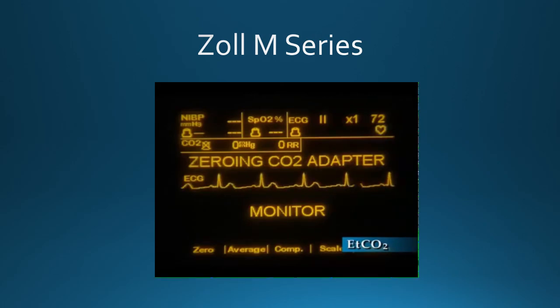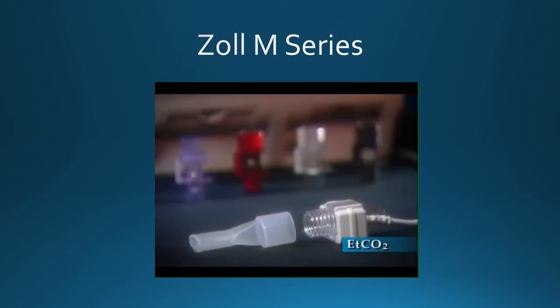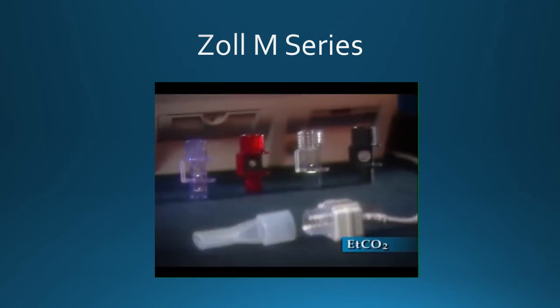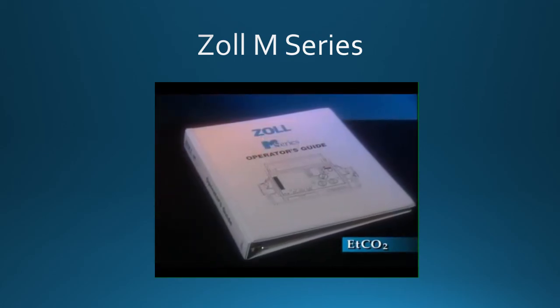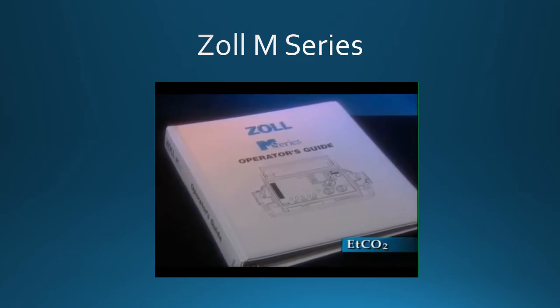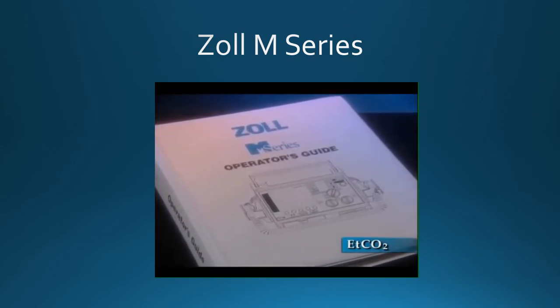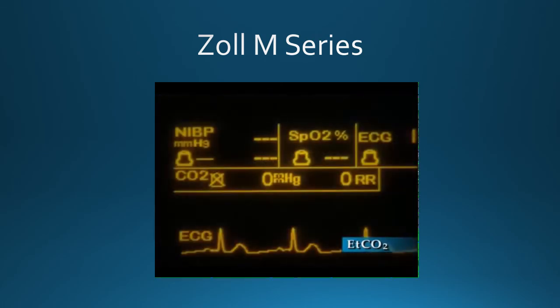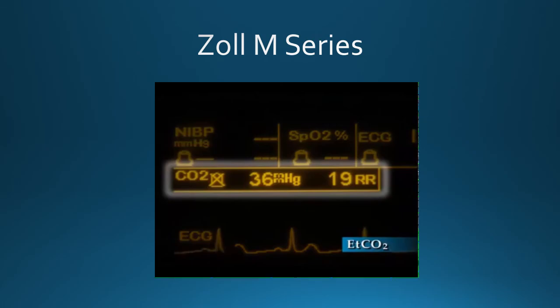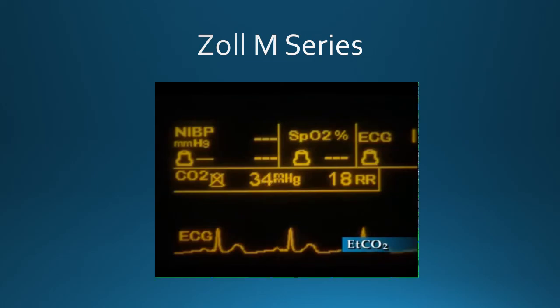An airway adapter zero will be required after switching between different airway adapter types, but is not required when switching between the same type of adapters. Multiple color-coded disposable and reusable adapters are available. Consult the Operator's Guide for assistance in selecting the proper adapter, adapter setup, location in the breathing circuit, and how to clean reusable adapters. The M-Series with the N-Tidal monitoring option monitors both CO2 and respiration rate. The results are displayed in the CO2 field located on the M-Series display. The maximum concentration of CO2 detected during each breath is displayed, along with the number of breaths per minute labeled RR.